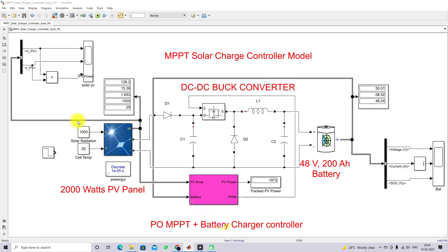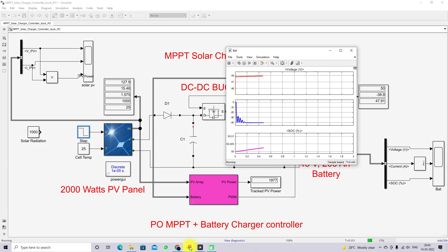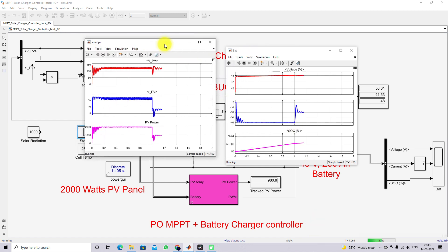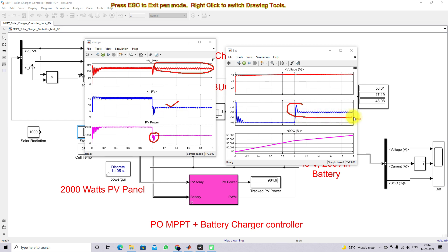Now applying the same condition to the P&O MPPT charging controller to check the results. Here you can see that because of the change in irradiation there is a lot of oscillation — this transient effect is not present in the fuzzy MPPT. In the P&O MPPT there is transient in PV voltage, PV current, and PV power during the irradiation change. The battery current also has some oscillation due to the change in irradiation.